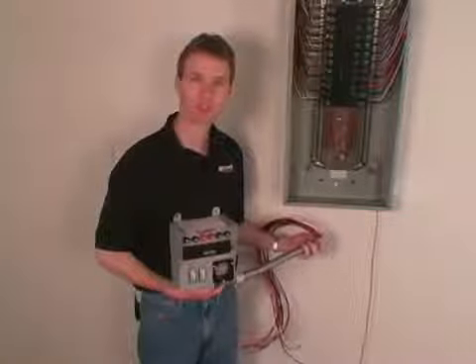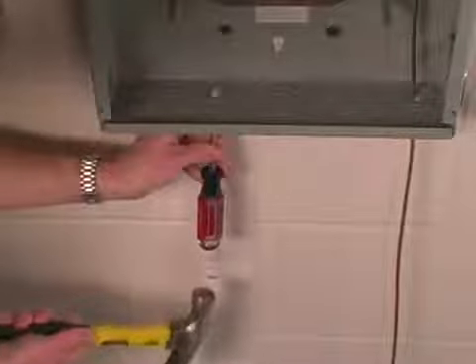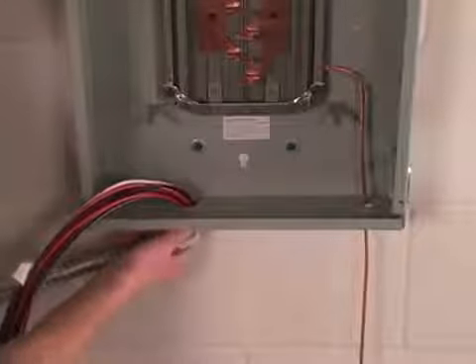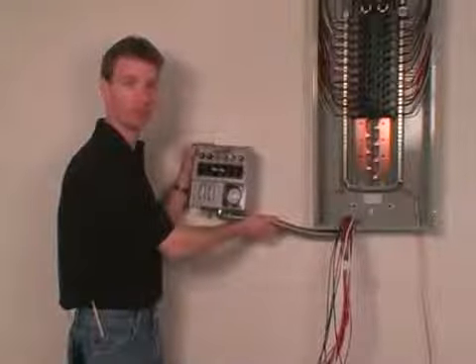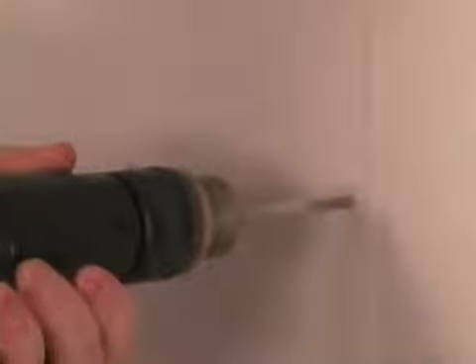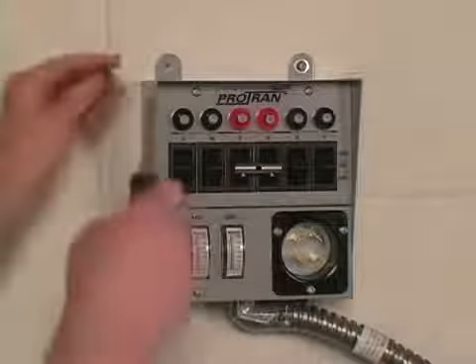To mount the transfer switch, we're first going to choose a 3/4 inch knockout in the bottom of the main panel. I've chosen a knockout close to the center of the bottom to make it easier to bring wires up each side of the panel. I'm first going to pull the wires through the knockout into the panel. Then I can snap the conduit fitting into the knockout opening. Be sure not to overbend the flexible conduit. Now we can mark the holes for mounting the transfer switch. Use appropriate anchors to securely mount the transfer switch.